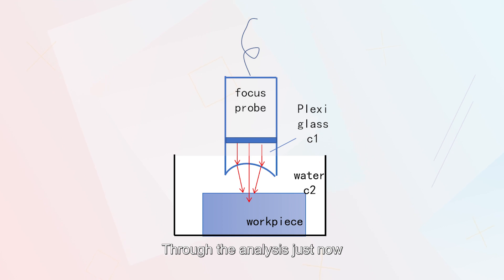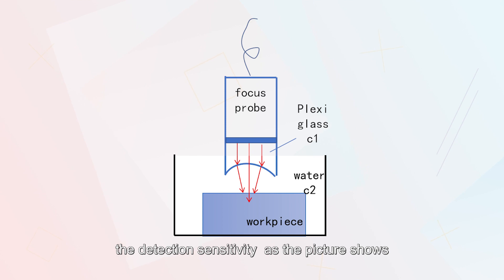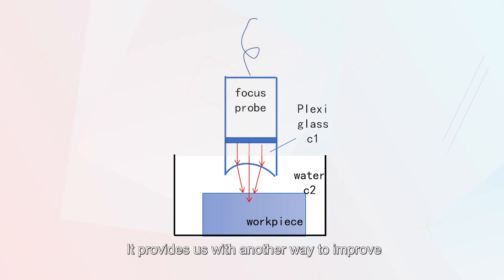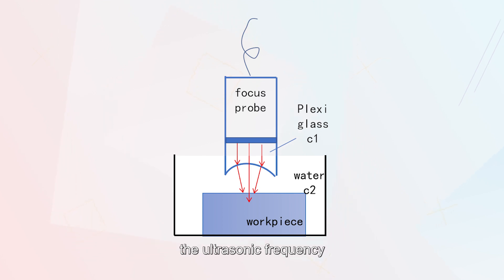Through this analysis, we can design a focusing probe to improve the detection sensitivity, as shown in the picture. This provides another way to improve detection sensitivity in addition to increasing the ultrasonic frequency.